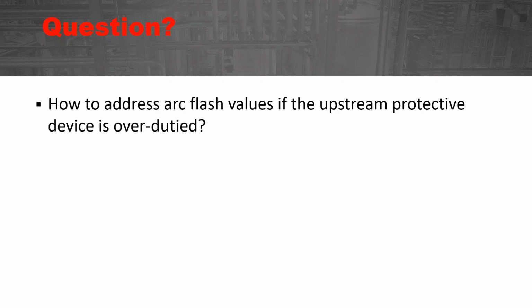How to address arc flash values if the upstream protective device is over-duty? This is for you, I think, Jay. Yeah, so the way I interpret this is how to address arc flash values or incident energy calculations that are high, also when the upstream protective device is over-duty. There's a number of things that are out in the industry right now to reduce the arc incident energy or to provide an adequate protection. So the first and foremost is you could replace the upstream device that's over duty. If they don't make anything available, another way you can modify the system, such as bus splitting, putting in an inductor or reactor to lower short circuit current values.